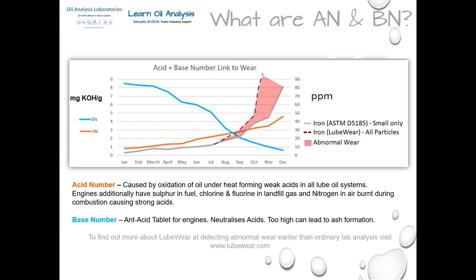Looking at the graph on screen, we start sampling a machine with a new oil change every month for a year without changing oil. In January and February the base number is high, the acid number is low, and wear is also low. You may notice the acid number does not start at zero — this is because additives react with lab test chemicals similarly to acids, giving a false positive. That is why a baseline starting point is important for trending. As time goes on, the acid number and base number come closer together, and eventually as they cross, the iron wear rate increases.